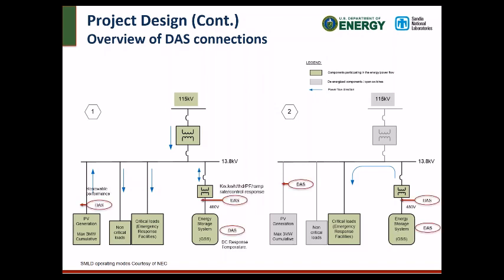What we're showing here is where you want to start collecting your data acquisition for different points on the system. On the left, if you are doing renewable firming, you need to make sure your data acquisition system is recording the PV output, as well as what's inside the energy storage system and what's at the AC portion of your energy storage.